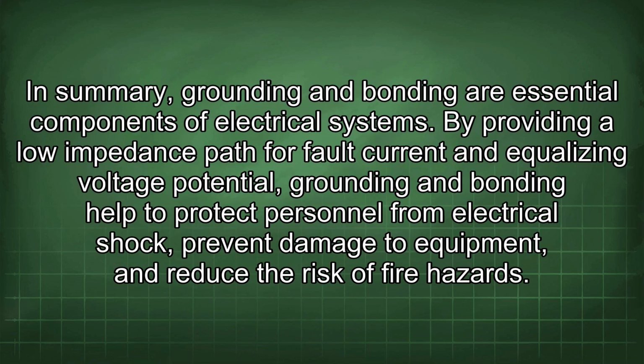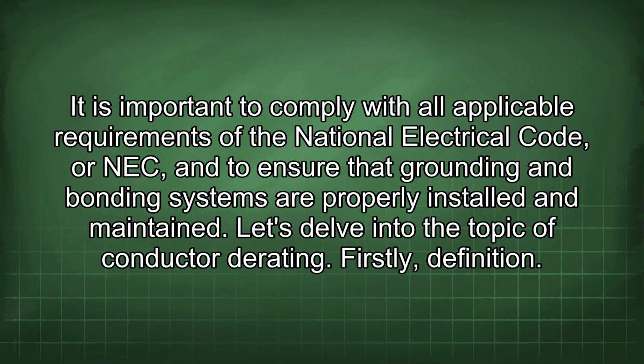In summary, grounding and bonding are essential components of electrical systems. By providing a low impedance path for fault current and equalizing voltage potential, grounding and bonding help to protect personnel from electrical shock, prevent damage to equipment, and reduce the risk of fire hazards. It is important to comply with all applicable requirements of the National Electrical Code, or NEC, and to ensure that grounding and bonding systems are properly installed and maintained.